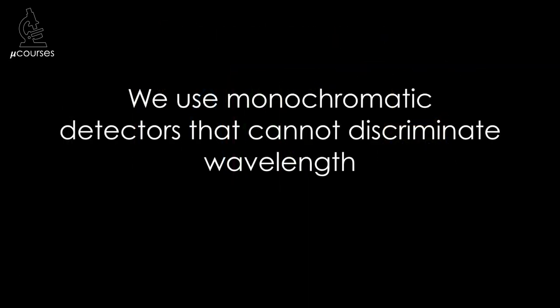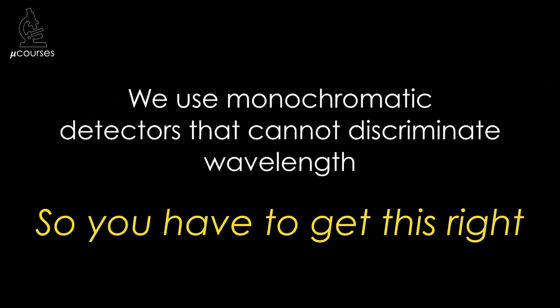Remember, we use monochromatic detectors such as cameras and photomultiplier tubes. These detectors report the amount of photons, but they cannot report the wavelength of photons. At the microscope, we rely 100% on fluorescence filters to achieve the molecular specificity that we expect from fluorescence microscopy.